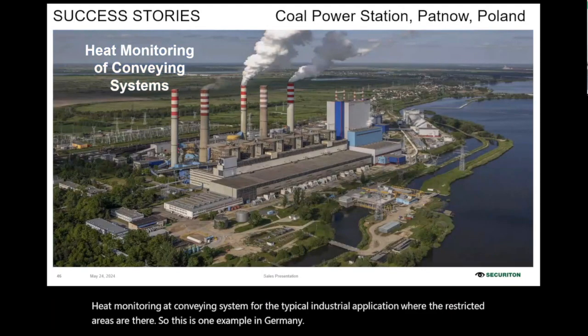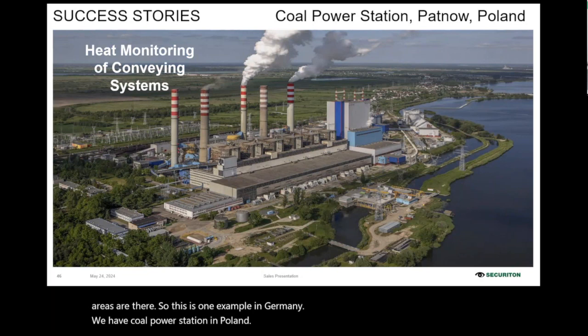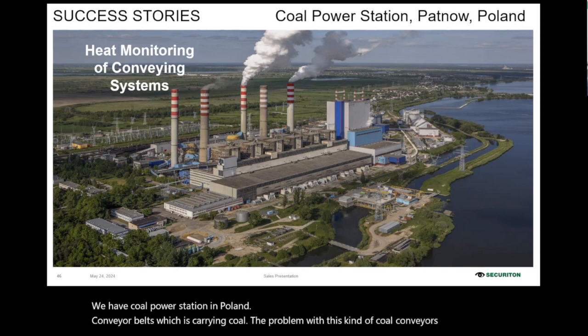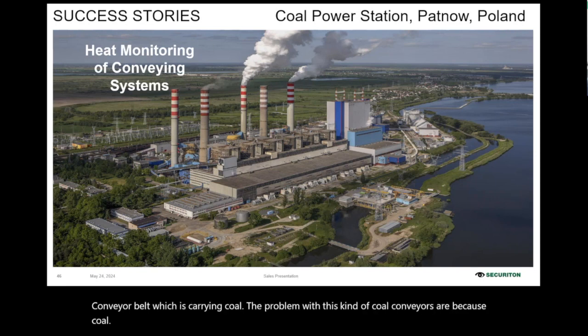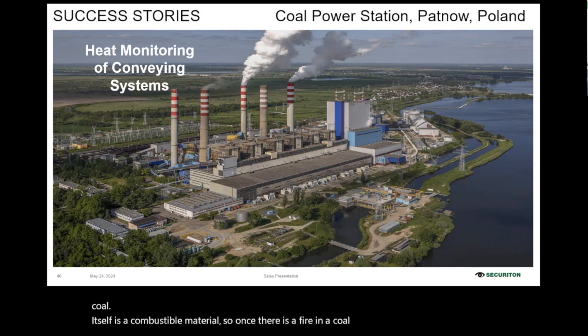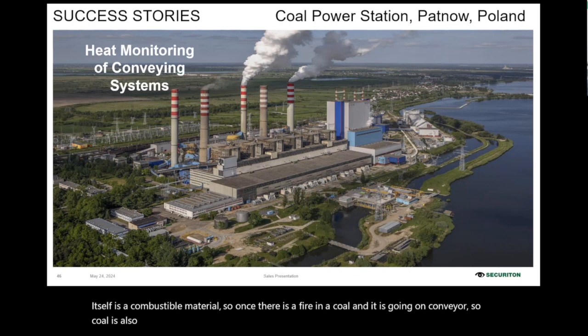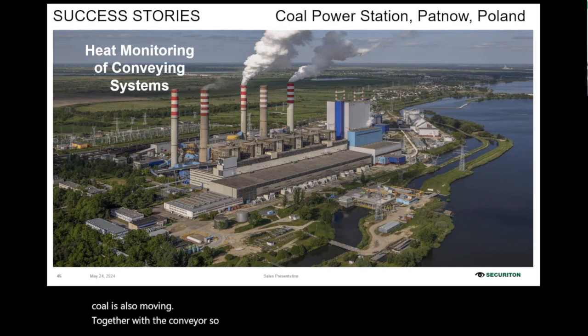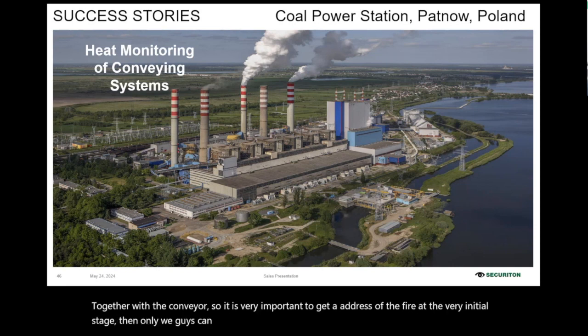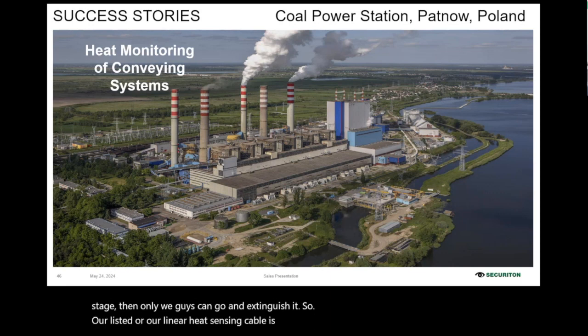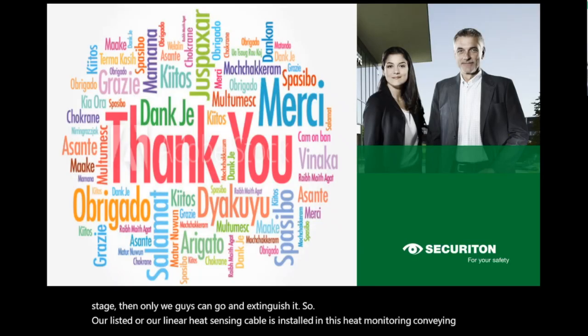We have a coal power station in Poland, with conveyor belts carrying coal. The problem with this kind of coal conveyor is that coal itself is a combustible material. Once there is a fire in the coal and it is going on the conveyor, the coal is also moving together with the conveyor. So it is very important to detect the fire at the very initial stage. Only then can we go and extinguish it. Our Listec, our linear heat sensing cable, is installed in this heat monitoring conveying system project. With this, I will end my presentation.